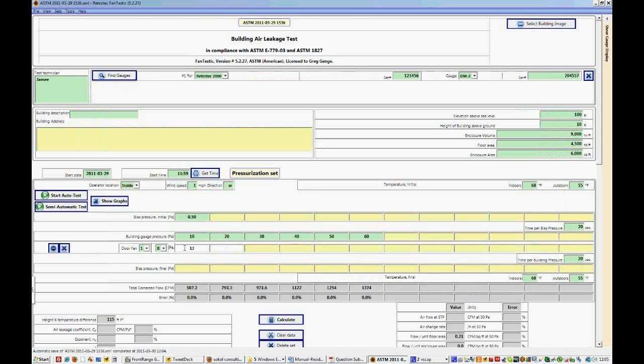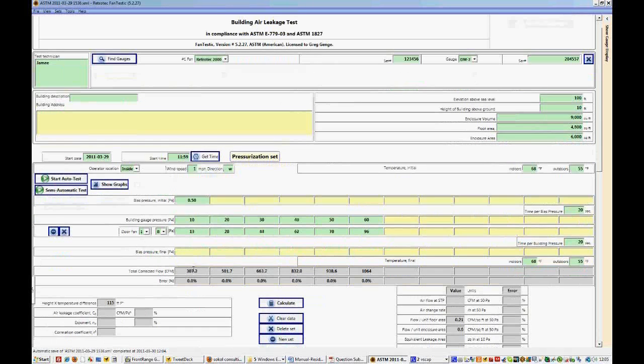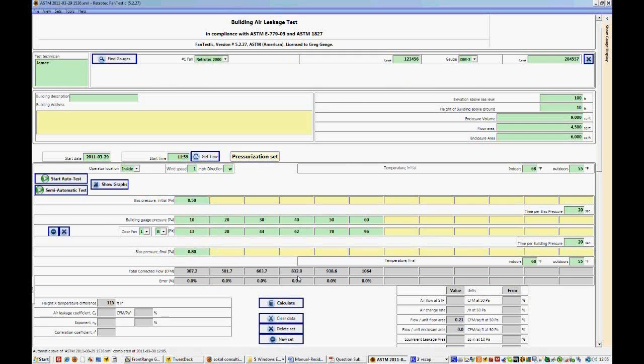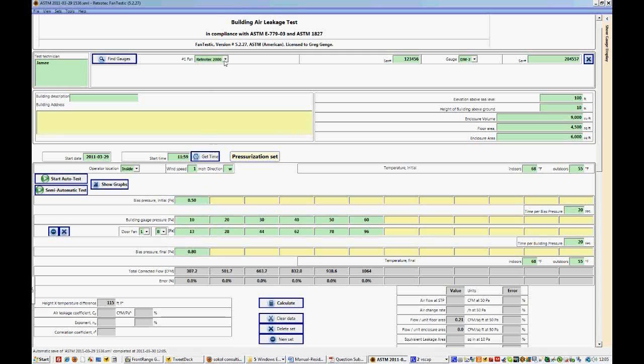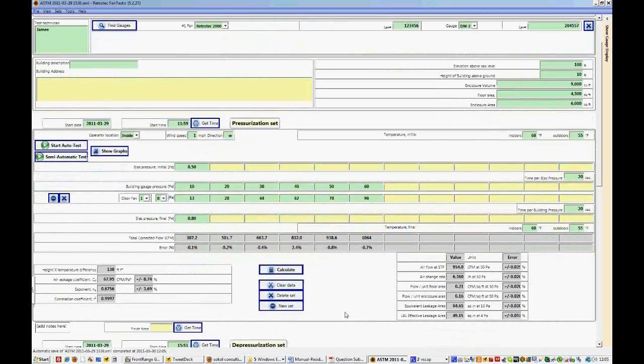Now we'll enter the building pressures that we took on range B. And we will enter as well the final bias pressure. And now you see that immediately these gray cells beneath the pressures that we have recorded are calculated. And the total corrected flow is calculated based on the flow curves for range B and for the RetroTec 2000 fan. So now if we push calculate we'll see all the results come through.